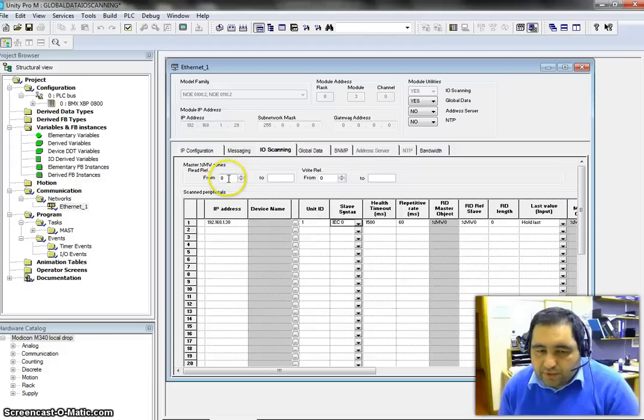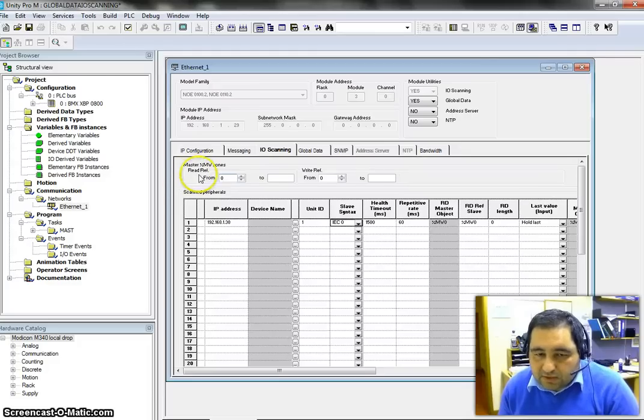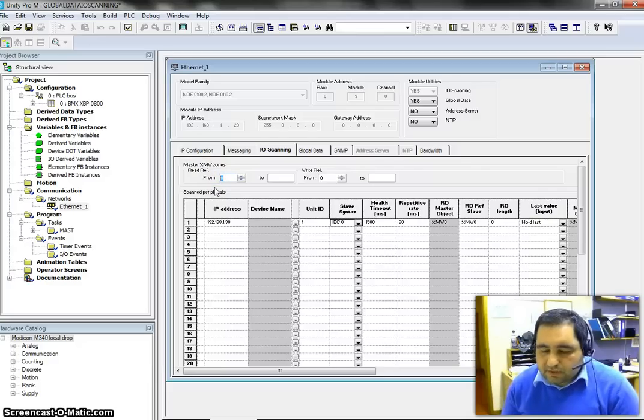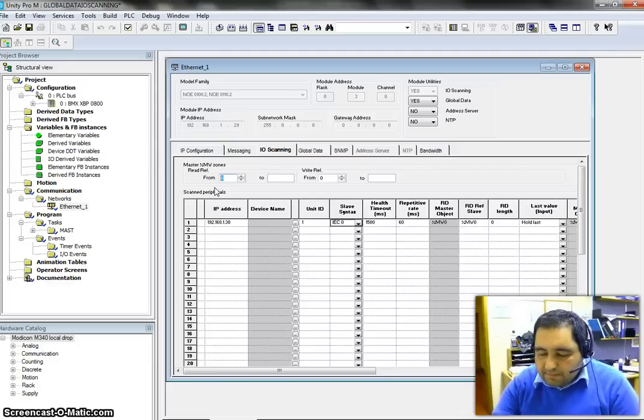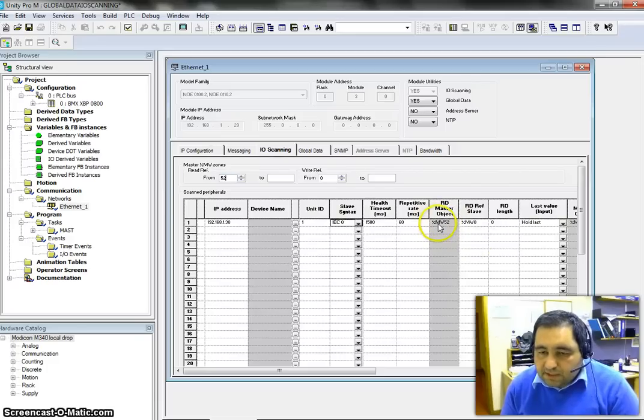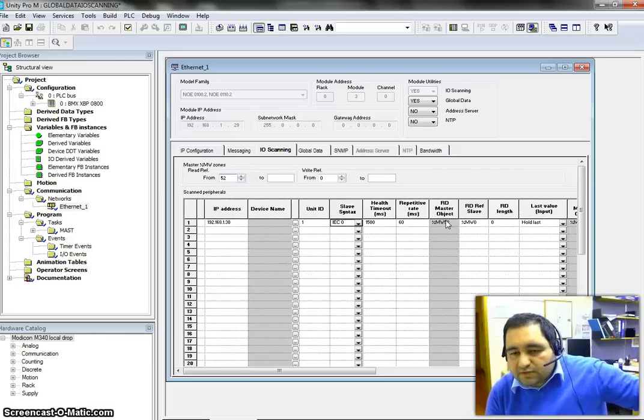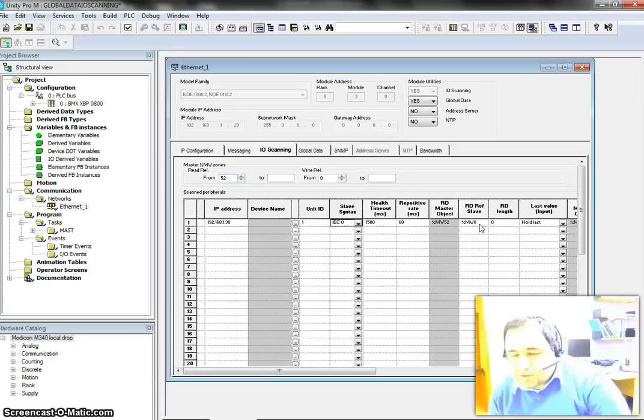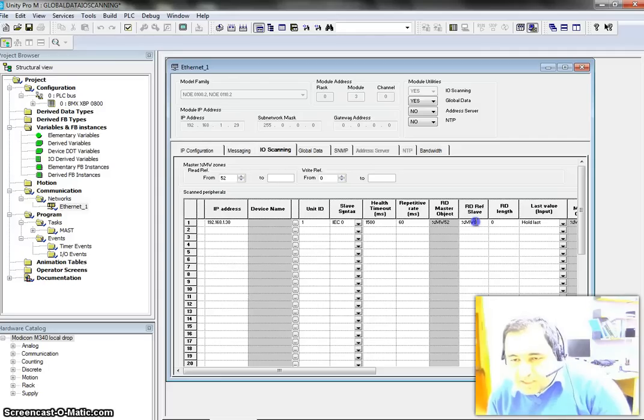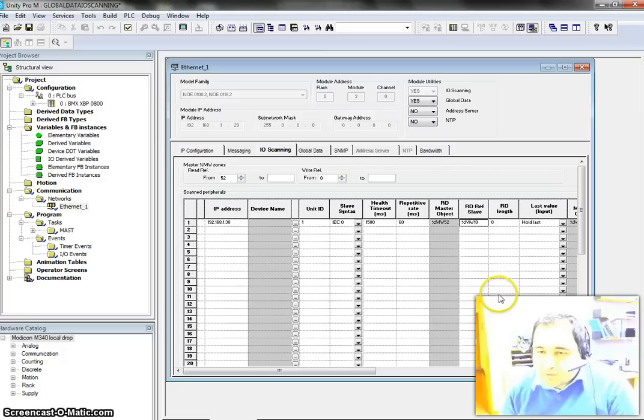After doing the initial settings we need to decide where to read and where to write. First, we decide where to copy the information we want to read, because we need to copy it somewhere in the memory of our PLC. Let's say it is memory address 52 — if we change it to 52 then the master object is going to be updated. Stuff stored in the slave device is going to be copied to the master. Then we choose which memory to read from — say memory word 10.